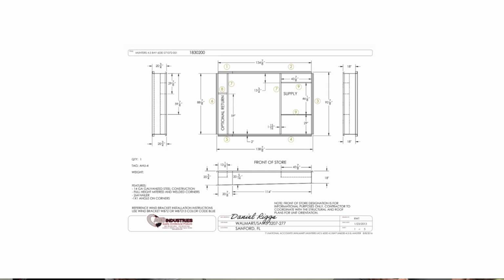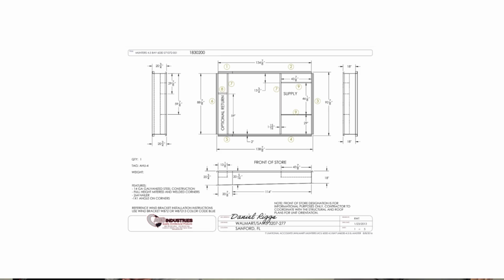But these pre-tapered curbs are much easier to install, period — if you have a curb pre-tapered to the roof, that's the best way to go. Measuring takes some doing because it has to be tapered, and you have to think about where the supply and return are going, how that correlates to the unit, to make sure you aren't tapering it the opposite way from what you wanted. You need to think through the fall towards the supply side or return side, whichever it is, so the taper — particularly if it's a two-way taper — goes towards the corner you want, or it just doesn't work at all.